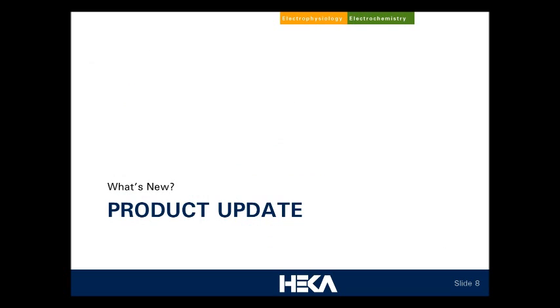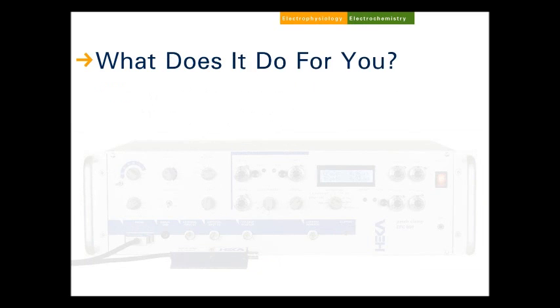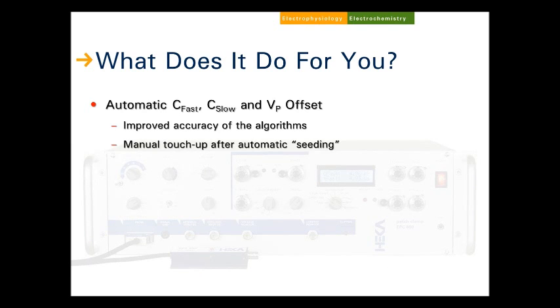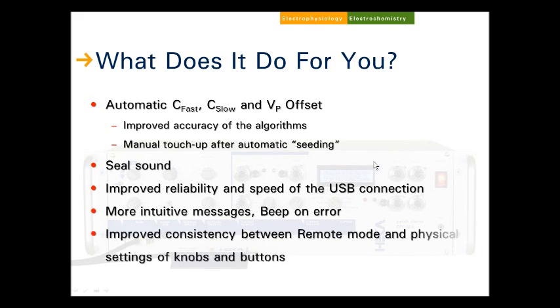Now I would like to discuss the product updates. First, the EPC-800, our dual-mode patch clamp amplifier, had a firmware update released in April this year. We have made improvements to the automatic C-fast, C-slow, and VP offset algorithms, and also to the auto functions with manual touch-up. The seal sound feature built into the EPC-800 has been enabled with this firmware release. We have improved the reliability and speed of the USB connection, added more messages to the LCD display and beep on error, and improved consistency between remote mode and physical settings of knobs and buttons.